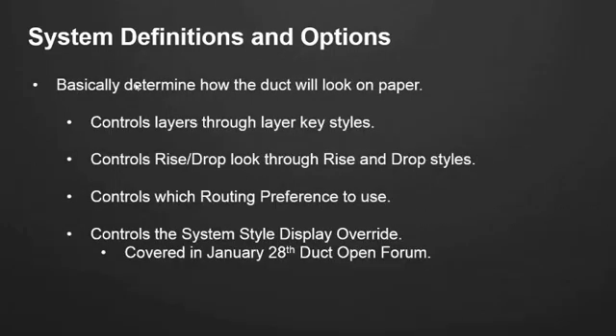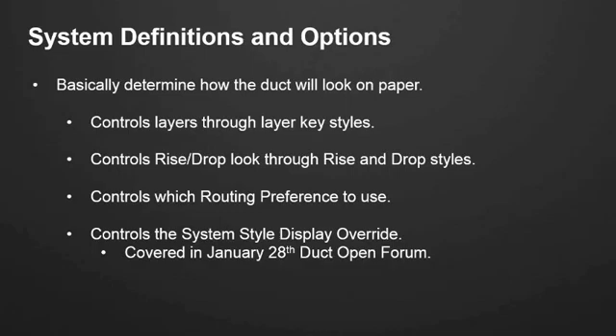A system definition basically determines how your duct will look on paper. It controls your layers through your layer key styles. It controls your rise and drop look through your rise and drop styles. In other words, when you're rising up through an elbow, what does that look like on paper? It controls which routing preference to use. So when you switch your system, you can automatically switch your routing preference. And it also controls the system style display override. We spent a couple of these open forums on the display system in the past. If you're interested in learning about that, then you can go onto our website on the portal. And if you scroll back to January 28th of this year, I did spend some time on system definitions. And you'll be able to then look at all the types of overrides, whether it's a system override, an object override, a style override, or your drawing default.